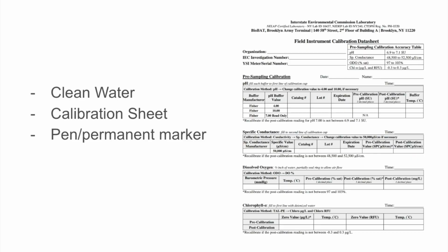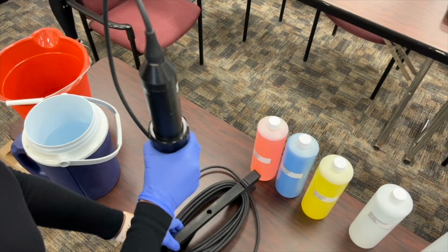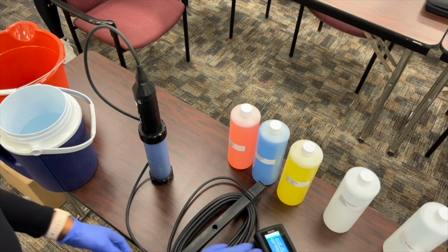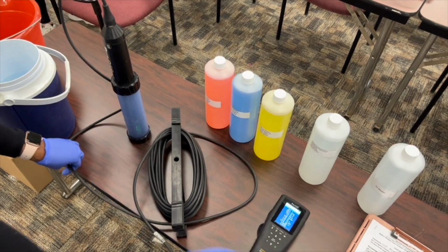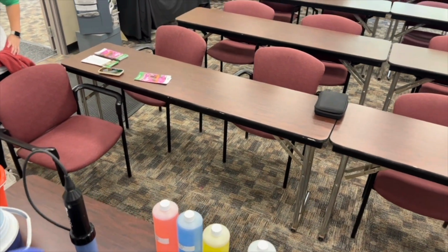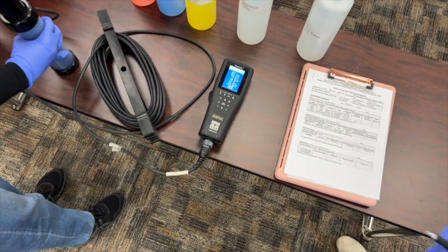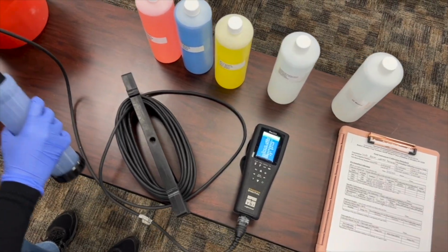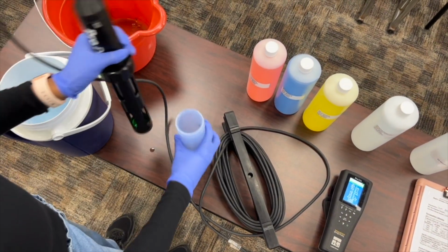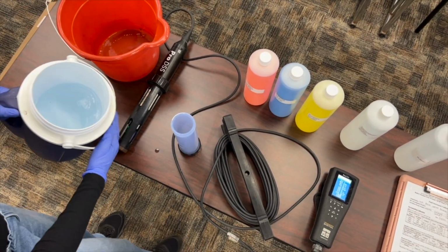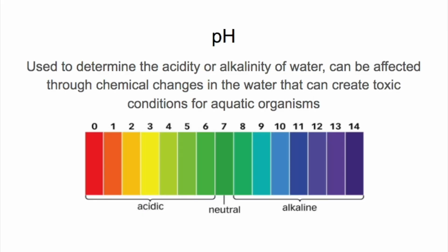To calibrate the YSI, you will need the following tools and equipment: YSI fitted with the appropriate sensors, calibration standards or buffers, these terms are used interchangeably, clean water, calibration sheet, a pen or permanent marker. Pre-calibration instructions. Before you begin, you should turn on the YSI at least 5 to 10 minutes ahead of time to allow the sensors to warm up. While the equipment is warming up, you can begin preparing other materials for your sampling day, including your calibration sheets, fresh water, and buffers. Calibration can be done in any order as long as conductivity salinity is calibrated before dissolved oxygen. First, we will calibrate for pH.